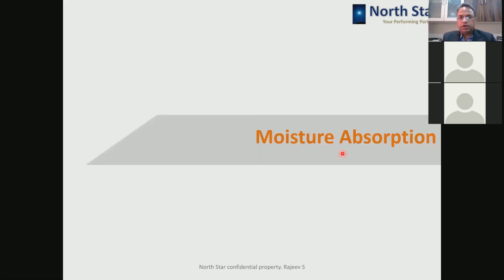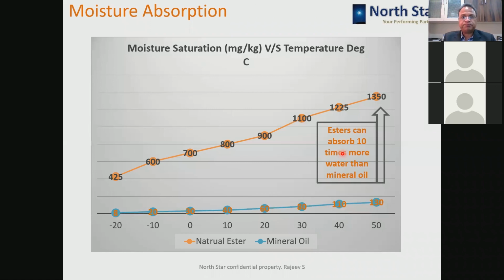Okay. Now let us look at the property of moisture absorption. So you can see the yellow or orange colored graph is for esters and the blue colored graph is for mineral oil. Here the temperatures are on the x-axis, and on the y-axis the moisture content is there. So for mineral oil, say at 10 degrees centigrade, you will see only 40 ppm, 40 milligram per kg moisture is allowed or within the safe limit. But for esters, it can be 800. So around 20 times more moisture can be allowed in a transformer with natural and synthetic ester. So esters can absorb at least 10 times more water than mineral oil.